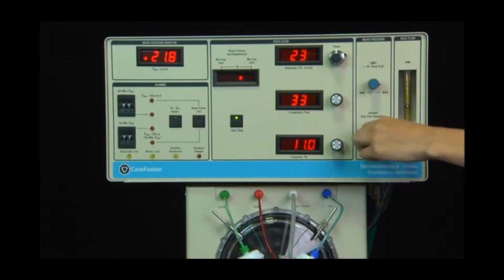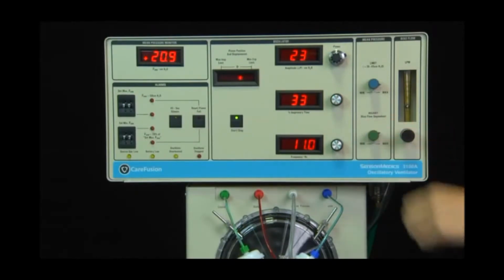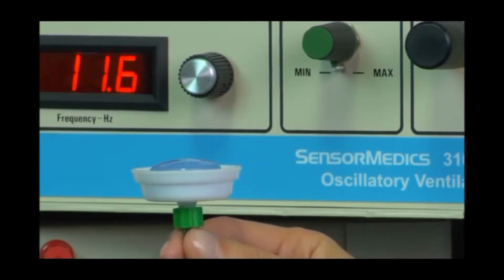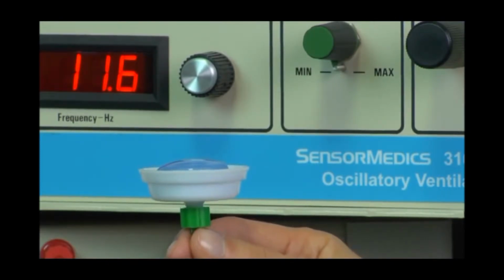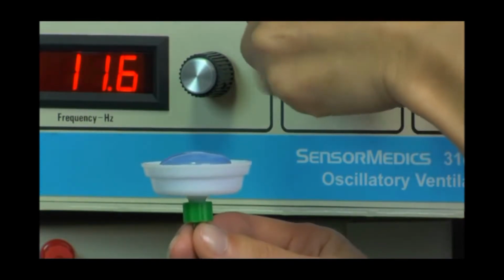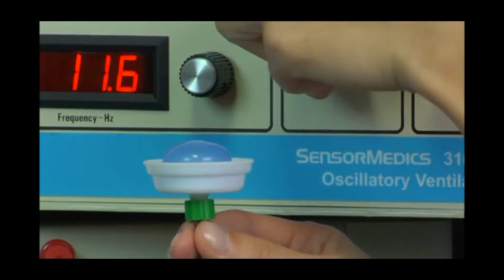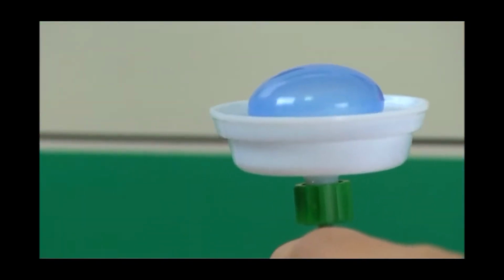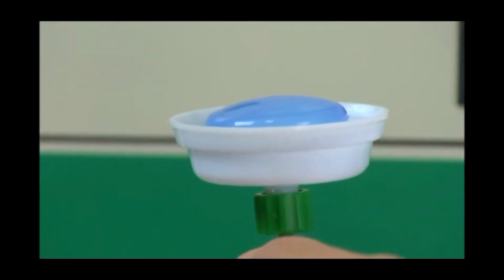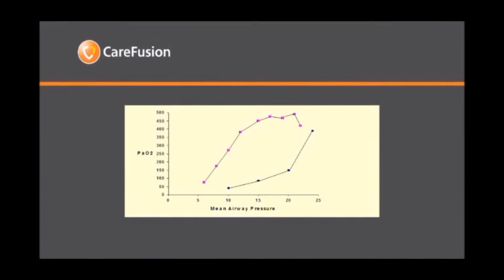The knob on the front of the instrument labeled Adjust controls the mean airway pressure. Manipulation of this control changes the inflation of the balloon valve on the expiratory limb of the circuit. This results in changes to the mean airway pressure. Mean airway pressure is utilized to establish lung volume and thereby directly affects oxygenation.